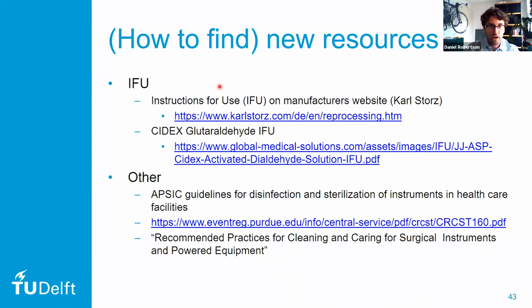The last one is the instructions for use, the IFUs. Most medical device manufacturers will have dedicated websites where you can look up information about the instruments that you have, and you can look up what recommendations they make for properly sterilizing them. So then you can look up whether the instruments that you have are safe to put into the autoclave, or that you have to do high-level disinfection on. And here are some other documents which are a bit more specific for laparoscopic instruments.